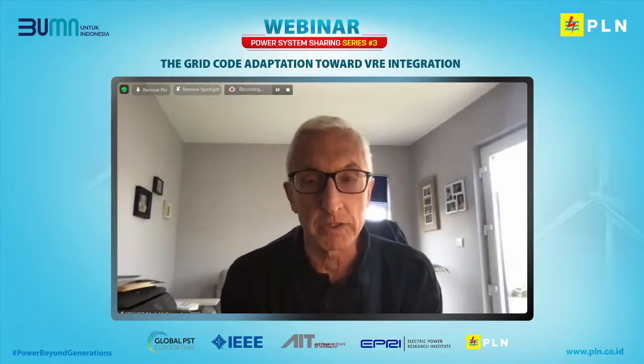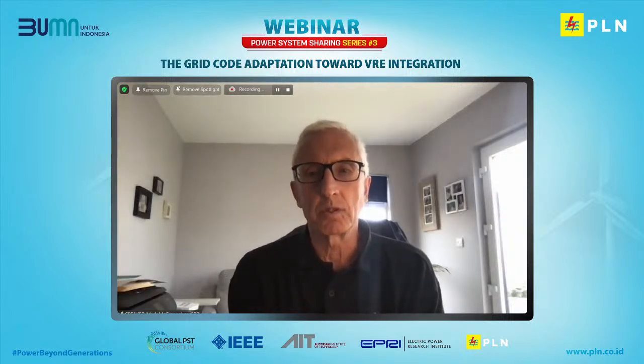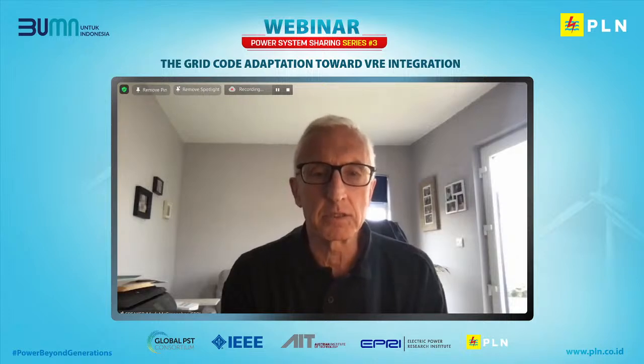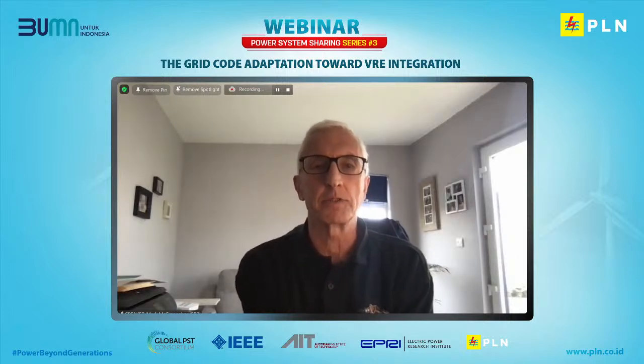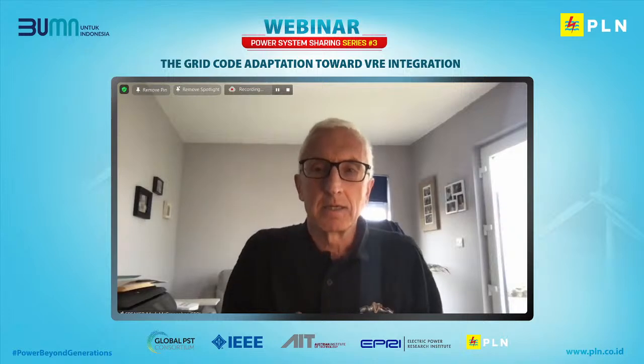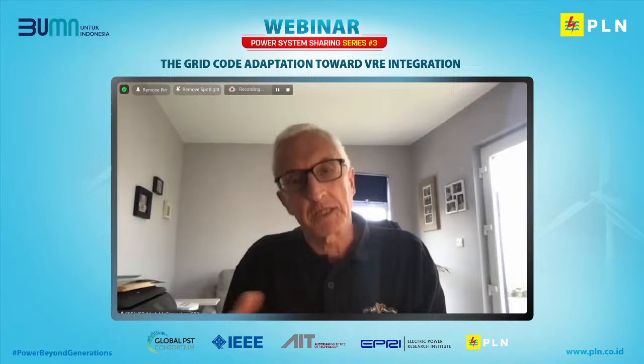If it's an energy storage device, then you can control both the reactive and the real power to help control the voltage. Those inverters have the capability to respond very quickly, so they can provide a benefit during the fault event to help support the voltage. But you have to look at it from a system perspective to make sure that response doesn't cause other problems. So it becomes a system study. But at least there's a requirement that the inverters have that capability if it makes sense for the particular system where they're being installed.